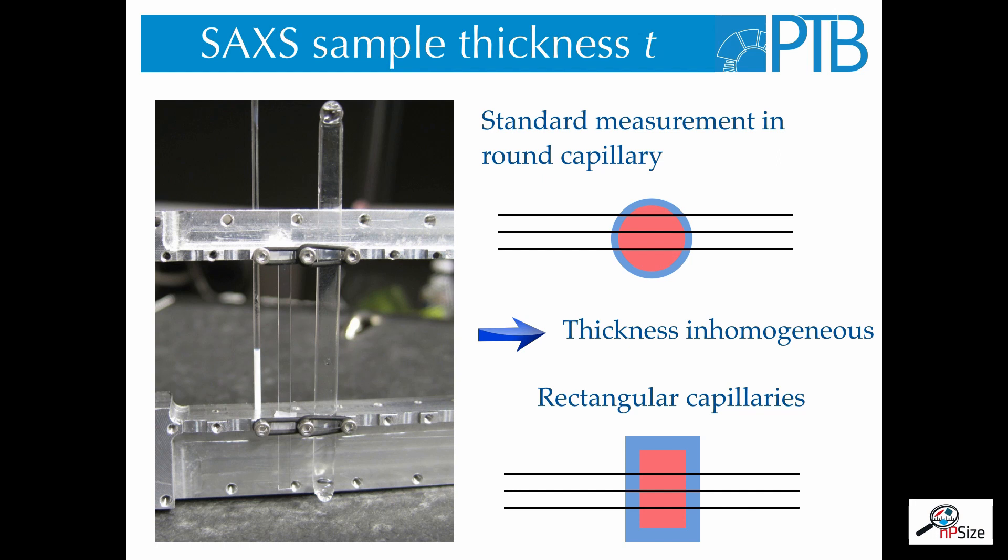The sample thickness is the optical path of the X-ray beam through the sample, the length of the optical path. Usually, we measure in round capillaries and there the optical path is not constant across the beam for the whole width of the beam. If we want to determine absolute units, we therefore use rectangular capillaries, where the sample thickness is constant over the whole beam.